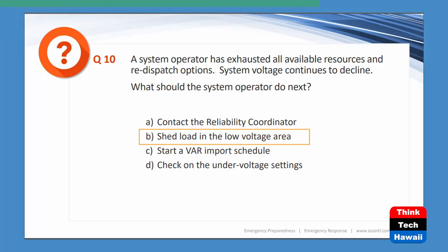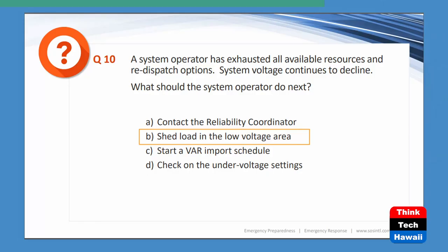A, contact the reliability coordinator. You probably already did that. B, shed load in the low voltage area. Okay, that's an option. Mind you, system voltage continues to decline. And remember, voltage declines happen in certain pockets, not throughout your system. If it begins to happen throughout your system, you've got some serious problems and you're just moments away from a blackout. C, start a VAR import schedule. That's not an answer. VARs do not travel very well. And then D, check on the under voltage settings. No, that's not what you do either. It's too late for that.